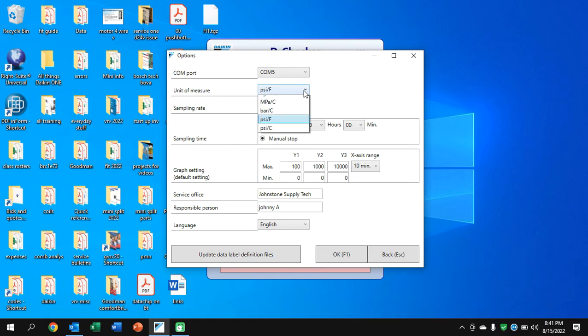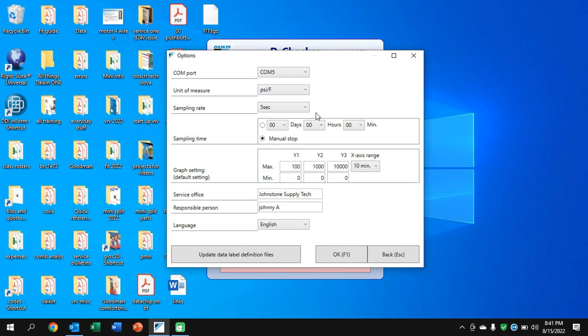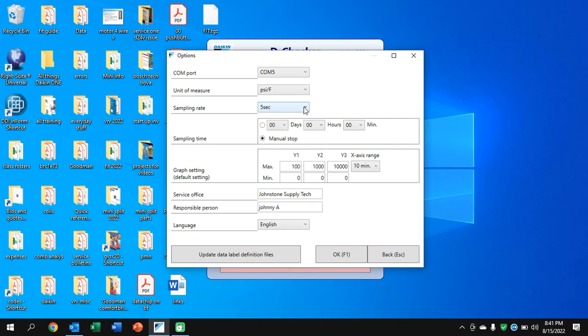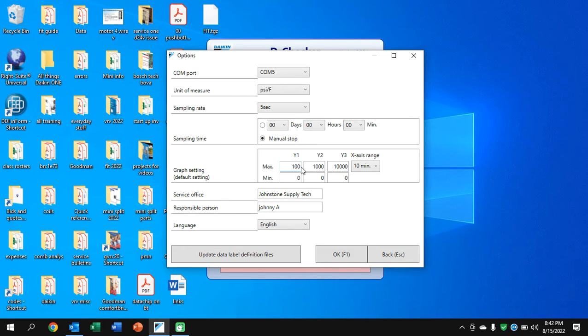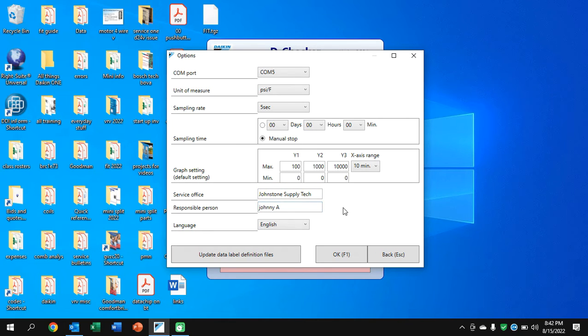But once you get it going, we'll go to options and we'll see the com port. If that's not visible when you plug it in and not visible under your device manager, you'll have to load the extra drivers. We also have some other items. You'll load your, in my case, pounds per square inch and Fahrenheit. I leave it on five seconds. I have plenty of memory. Leave it to manual stop. I don't worry about the graph settings. I'll go back and do those when I'm actually in the graph. But the service office and responsible person must be filled in or it's not going to let you continue.